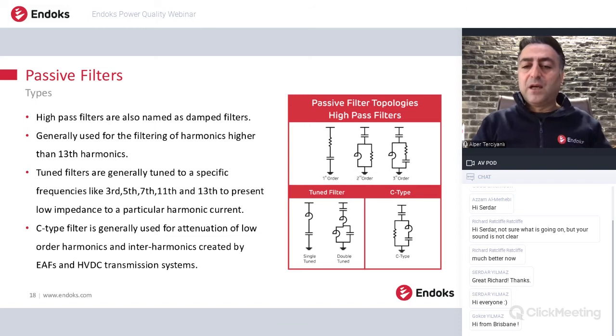pass filter can eliminate not only the second, third, or fifth harmonics. We can also eliminate the interharmonics generated by the arc furnaces and the high voltage DC transmission systems. As you see in these passive filters, we have only passive elements: inductor, capacitor, and the resistor. So with some different variations of this equipment, we can create filters. But since we are using capacitors in these filters, we are using the passive filters not only for eliminating harmonics, but also for balancing or compensating the reactive power and as a reactive power source.